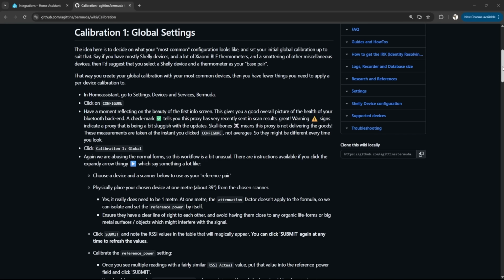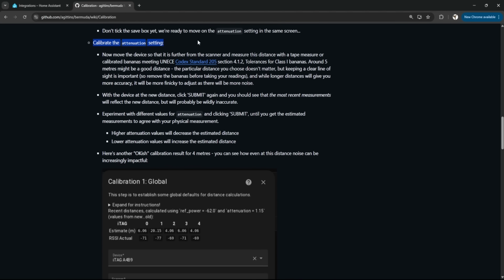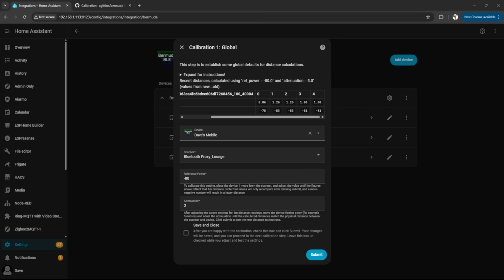Back to the documentation page, if I just scroll down, we are now at this stage where we're going to calibrate the attenuation settings, and you will need to move your device 5 meters away from the scanner. Then press Submit, and we need to tweak the attenuation settings to get the reading closest to 5 meters. The higher the attenuation value, the shorter the estimated distance, and the lower the value, the greater the estimated distance. Now it doesn't have to be 5 meters, that's just a sweet spot. So I'm just going to quickly move my device so it's 5 meters away. Now that the device is 5 meters away, I'm going to click Submit, and I should see these values here are going to completely change.